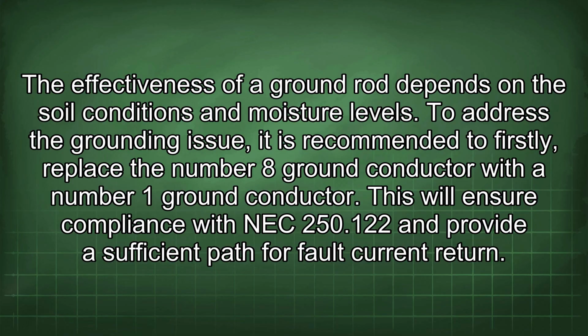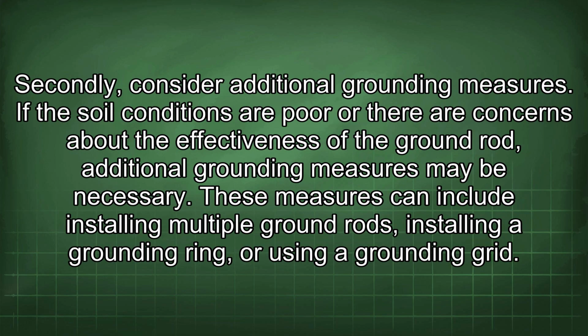To address the grounding issue, it is recommended to firstly replace the number 8 ground conductor with the number 1 ground conductor. This will ensure compliance with NEC 250.122 and provide a sufficient path for fault current return. Secondly, consider additional grounding measures. If the soil conditions are poor or there are concerns about the effectiveness of the ground rod, additional grounding measures may be necessary. These measures can include installing multiple ground rods, installing a grounding ring, or using a grounding grid.